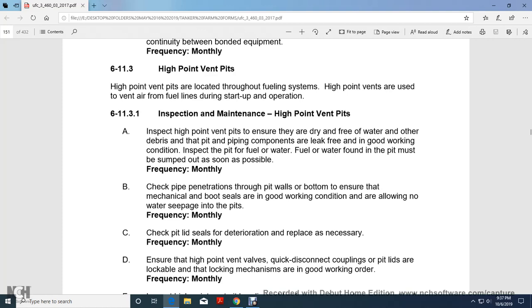Inspect the high point vent pits to ensure they are dry and free of water and debris, and that the piping components are leak free and in good working condition. Inspect the pit for fuel and water. Fuel and water found in the pit must be sumped out as soon as possible. Monthly, check the pipe penetrations through the pit walls and bottom to ensure the mechanical boot seals are in good working condition and allowing no water seepage into the pits.